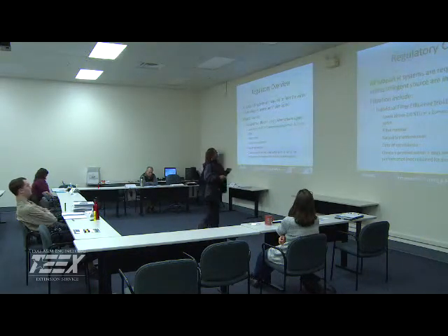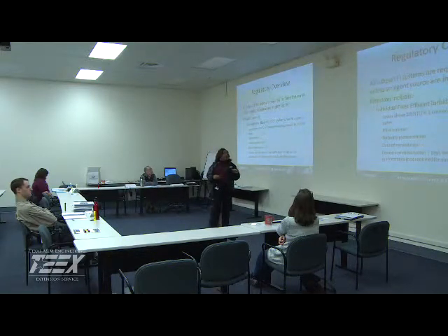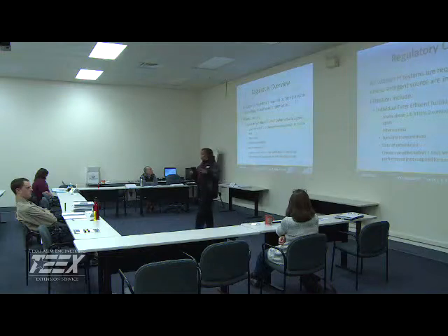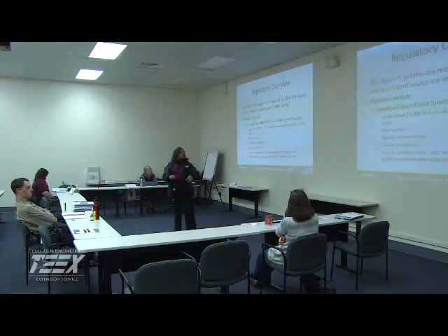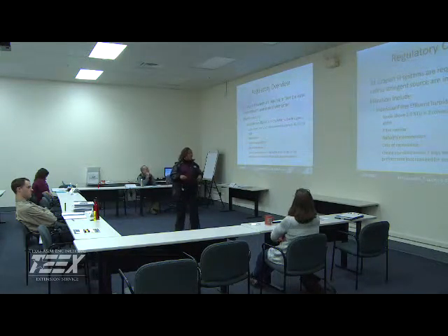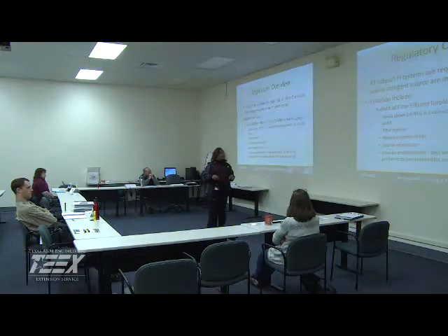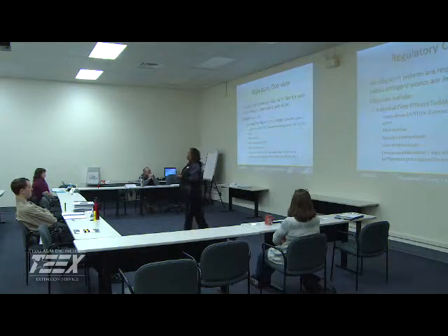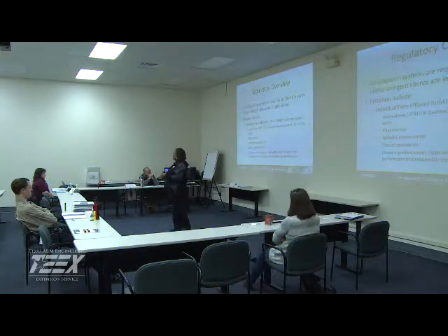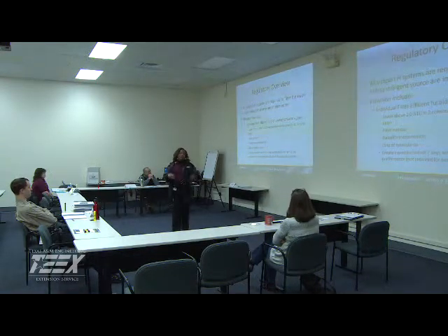The information you want to make sure you're getting to the agency is whenever you have levels above 1 NTU in 2 consecutive measurements, 15 minutes apart. That has to be reported. You're going to let them know the filter number, turbidity measurement, and the date of the exceedance, and you may be asked to create a profile within 7 days for the abnormal performance. The reason I say you may be is that it depends on the size of the system. Larger systems are required to do this, smaller systems at the discretion of the state agency.